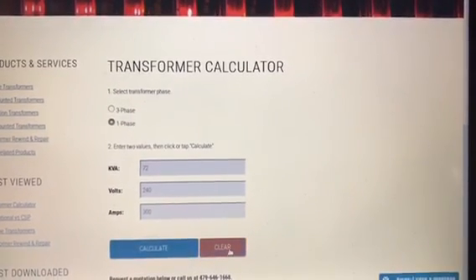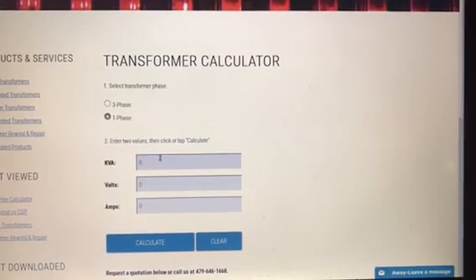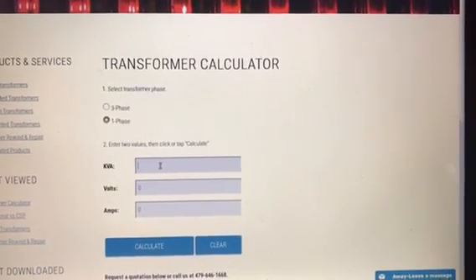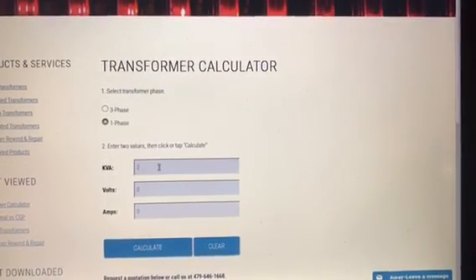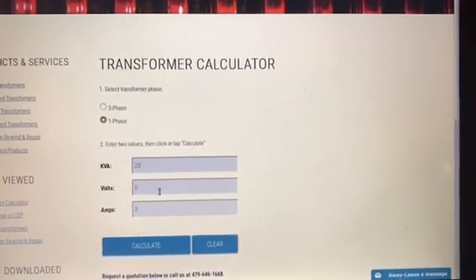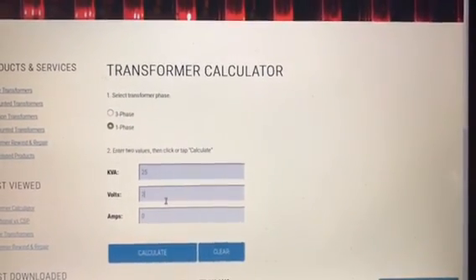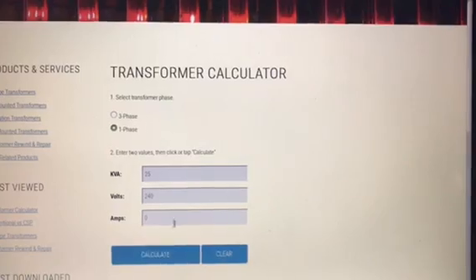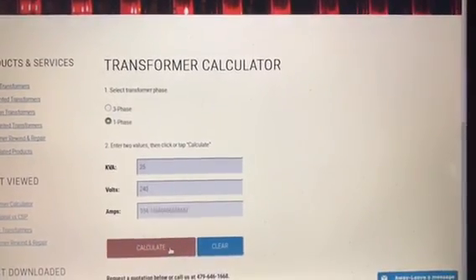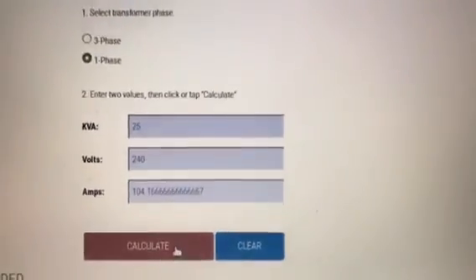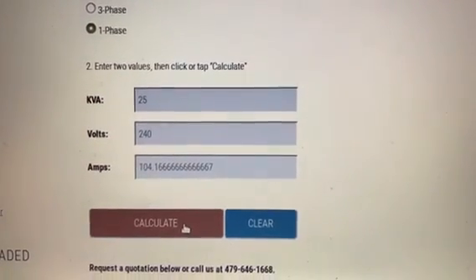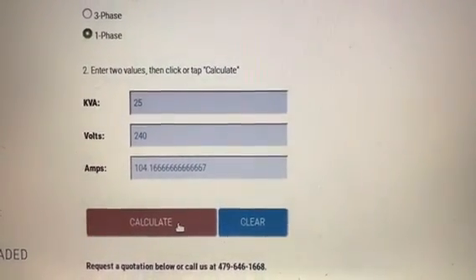This calculator works in a couple of different ways. So let's say the service in this video has a 25 kVA transformer, and we're at 240 volts. When I hit calculate here, you're going to see that a 25 kVA transformer is only rated for 104 amps continuous.